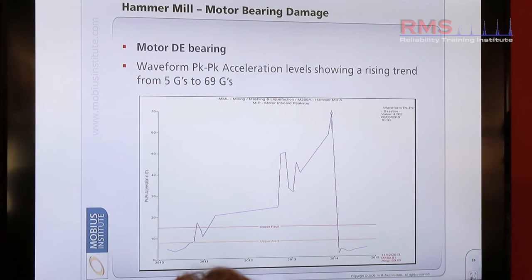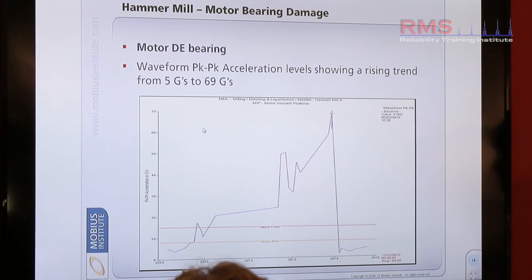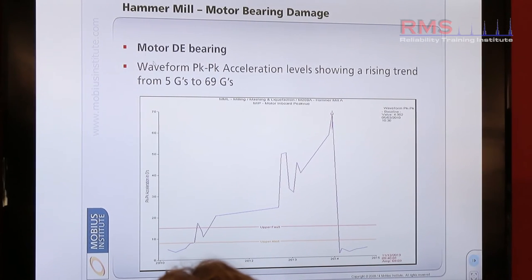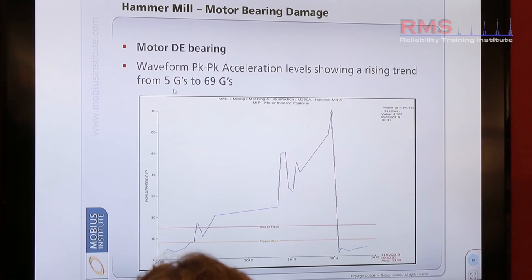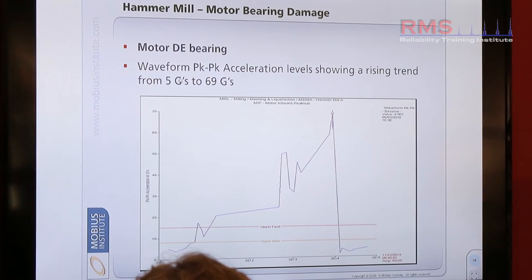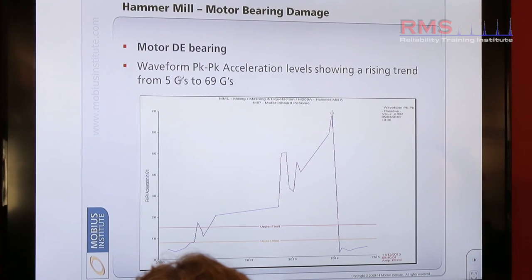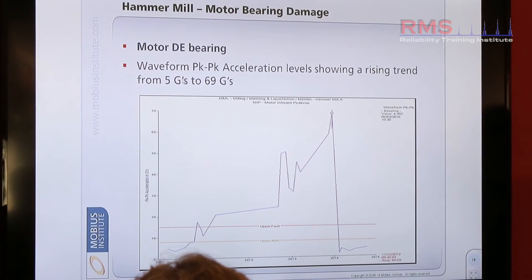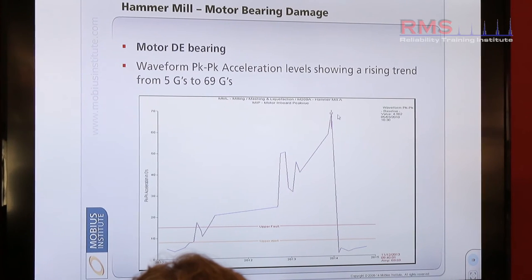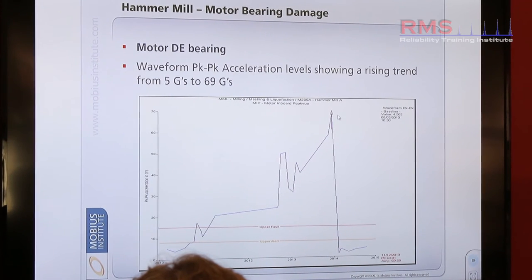Where at the baseline — the first measurement taken here — it's 5G. That's kind of quite reasonable. It's a peak-to-peak measurement of the shock of the signal up to 70 Gs. You can see the degradation there is up to 70 Gs.